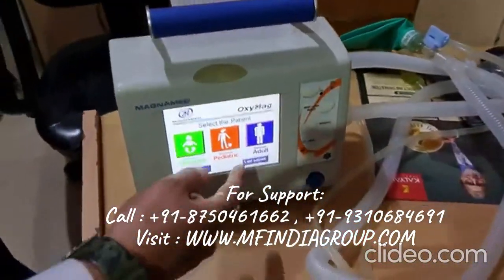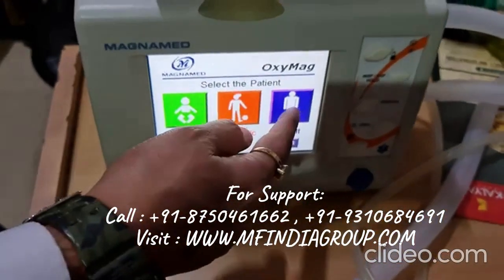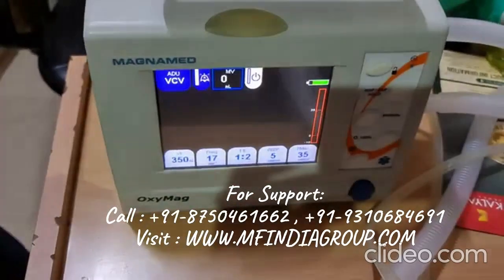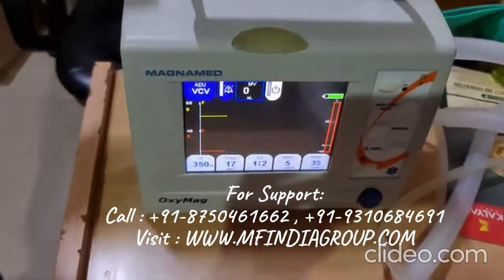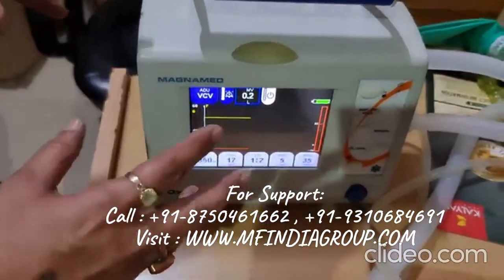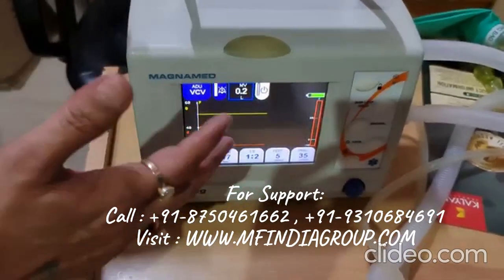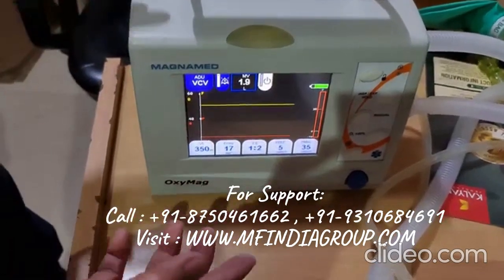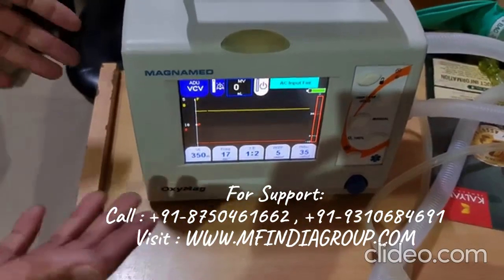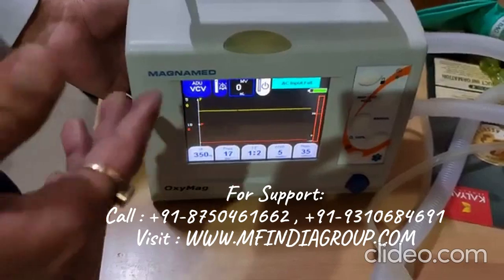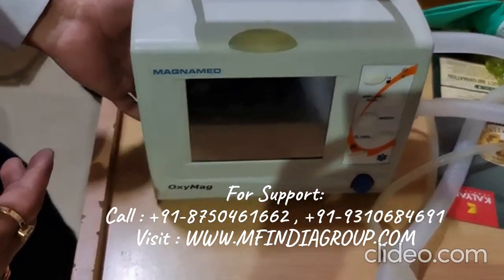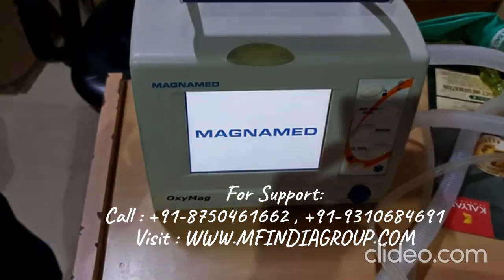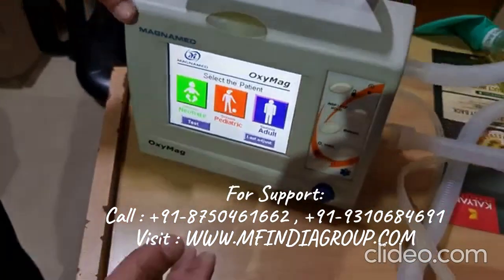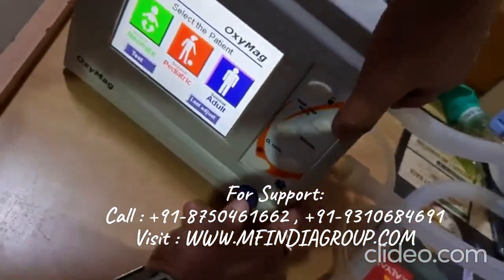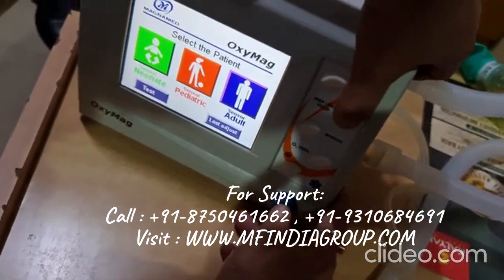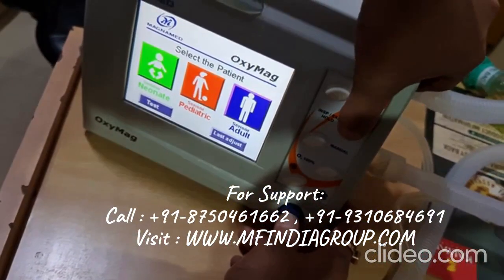So after that, whenever you touch the patient, say adult, it will start ventilation immediately. So no need to adjust and preset and all that. According to the patient, the preset parameters will work and ventilate. It will start ventilating. If you want to change the patient, then you have to switch it off and switch on again. Now we will see this in demo mode. For demo purpose, you have to hold this, press these two buttons simultaneously.